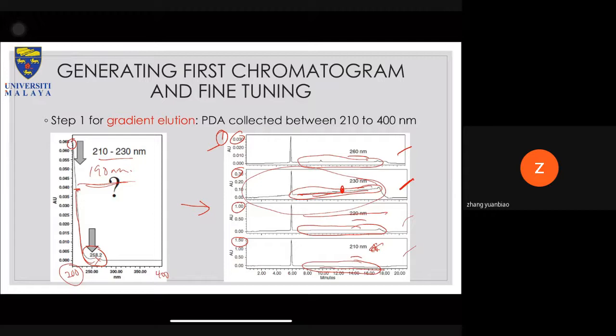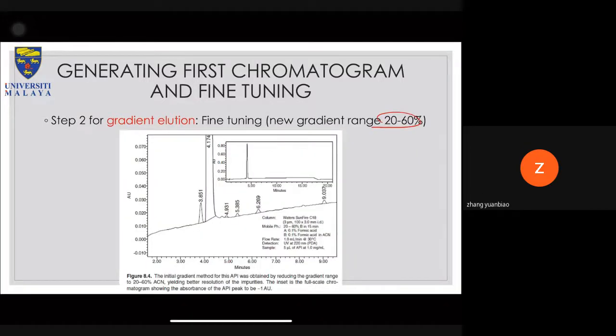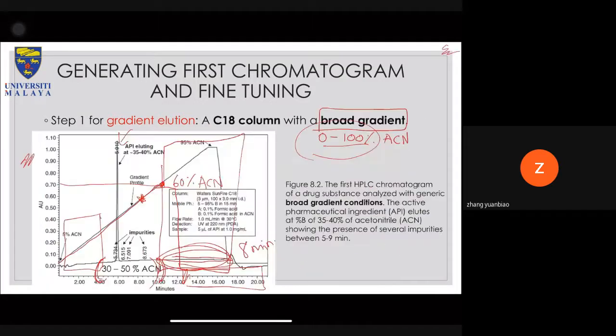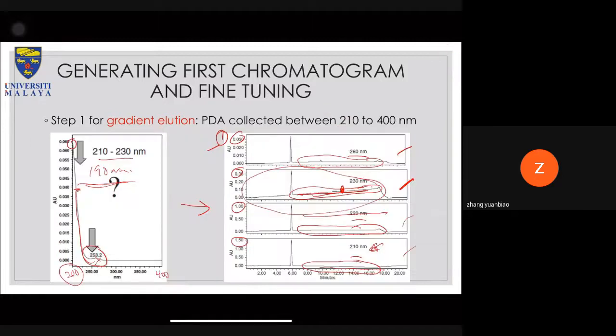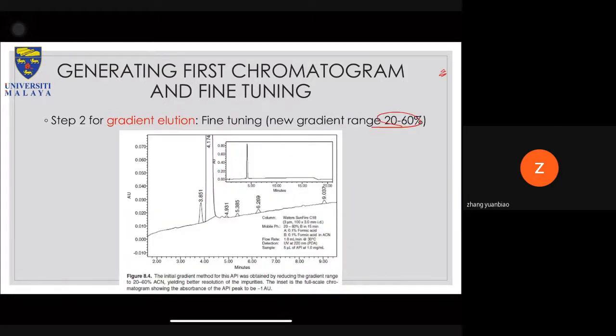So step 2 for gradient elution is the fine tuning. So a new gradient range. This is in conjunction with this slide. Okay, remember this slide? When you do fine tuning for your gradient elution, the example shown here is 20 to 60%. I should have put an image here. The previous slide shows a rather pure sample, but when you fine tune, not only can you save time and solvent and whatnot, you might also get a better method run that can identify impurities if they exist underneath the peak.